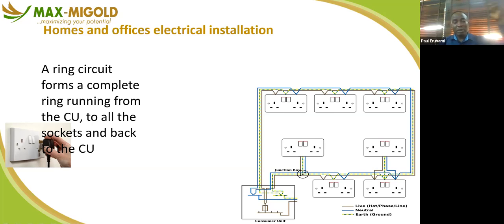The same thing with some ACs. You run them directly from the distribution board, though they consume more wires or cables, but in the long run, you are actually investing to save cost. No socket is overloaded, unlike the ring, where you may feel it is a 30 amp socket. You then bring a multiple socket and plug into it. You plug your fan, you plug your electric kettle, you plug so many things on it, and you are causing that socket to go bad every now and then. So that's what you should know.